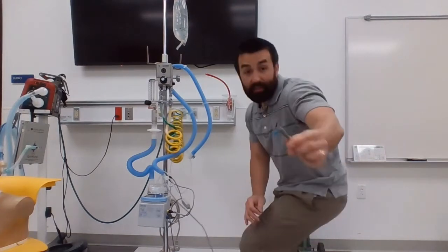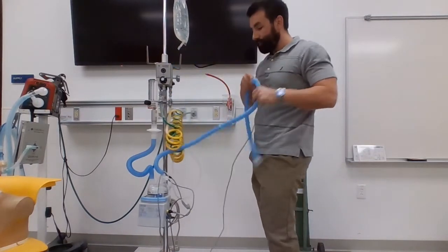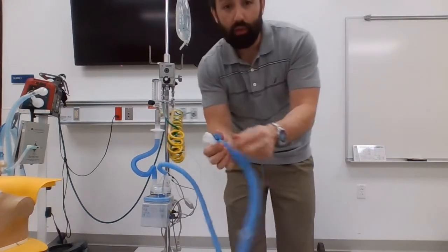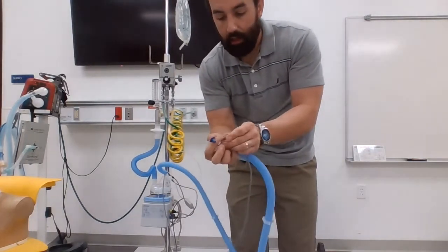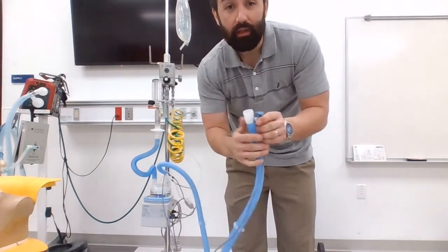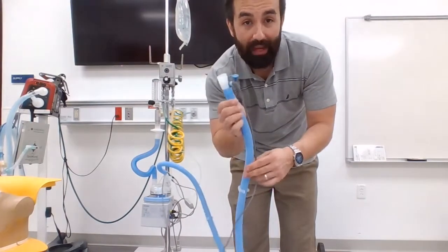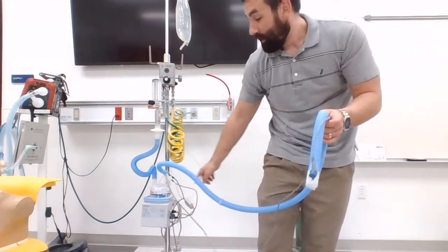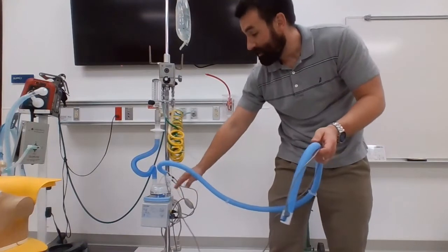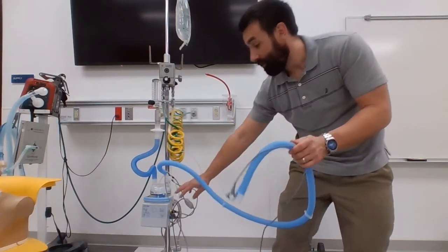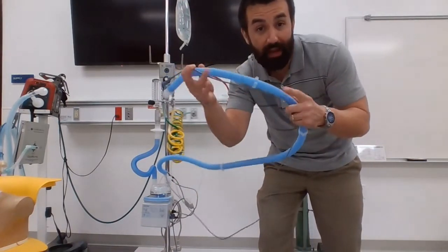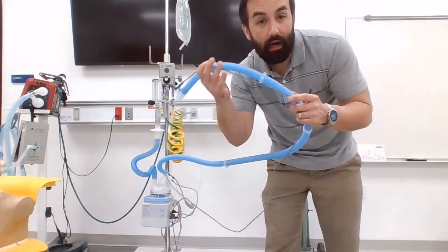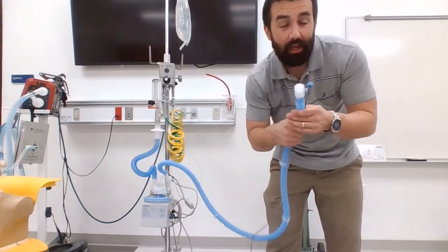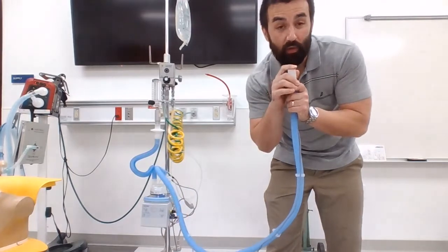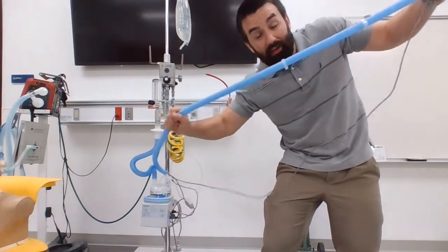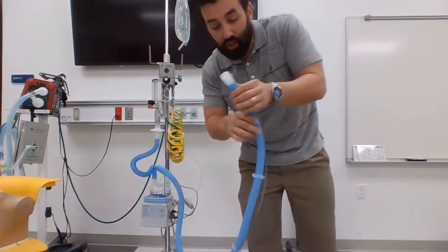We're going to take this line, the longer one, and we're going to open up this little blue port. This is the temperature probe. So it measures the temperature right before that gas goes to the patient. Okay, so this one back here is telling the heater what it needs to do. The temperature probe here is telling the heater what it needs to do in regards to maintaining the temperature of this inspiratory line for our patient. So this is what is going to measure what's going to the patient, and it's going to condition that gas, keep that gas conditioned by adjusting the charge inside of this thing.